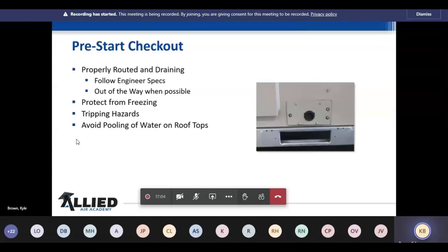And then tripping hazards. If you're like me and you walk up on a roof and you've got your mind on things, at some point in time we all have tripped over a drain line and broken a trap off. If I had $1 for every time I did that, I wouldn't be talking to you today. So make sure they are routed in a good spot where you're not going to do that. And make sure you avoid it pooling on the roof, because when the roofers come up and look for roof leaks, the first thing they're going to blame is this unit. So make sure we route these things to a roof drain or a proper drain or to where the engineer specified for us to put these drains. Water damage causes a lot of issues, and it's so simple and easy to avoid.